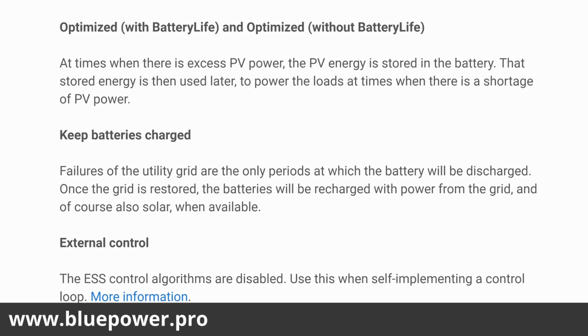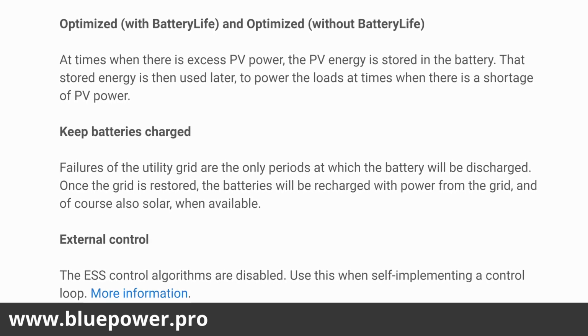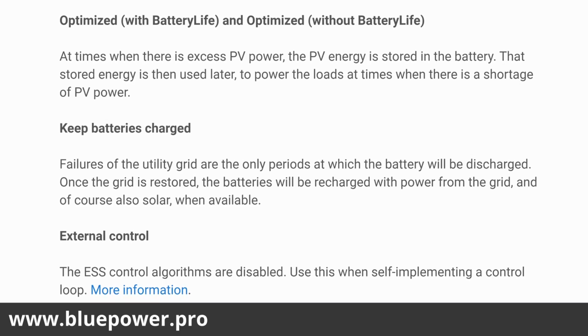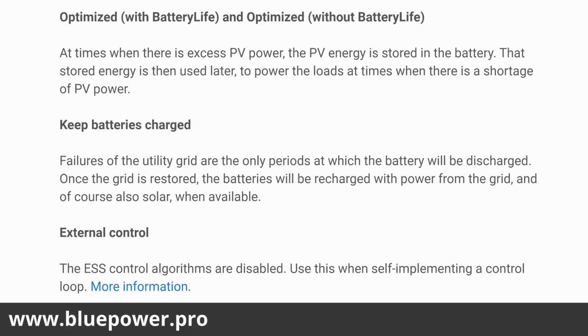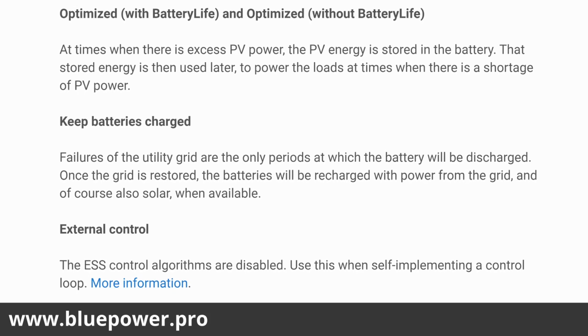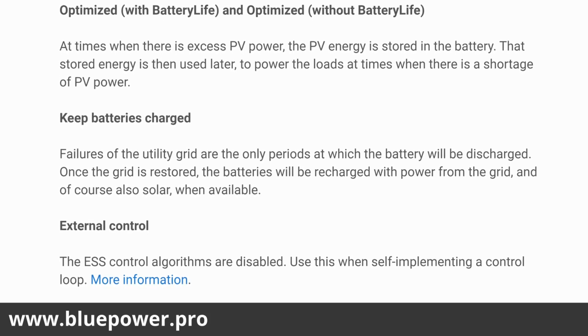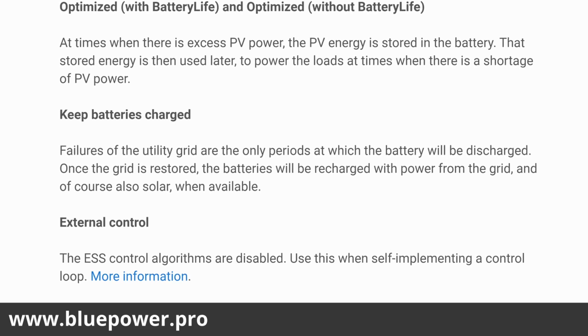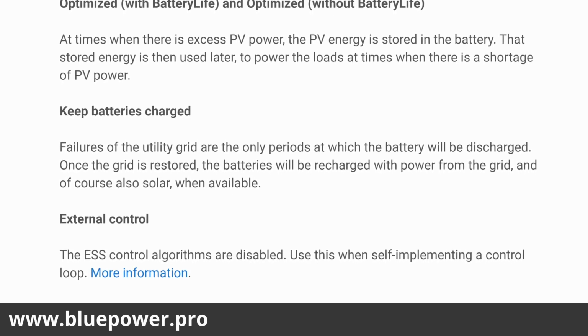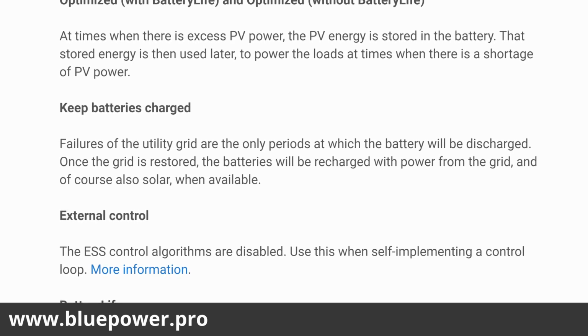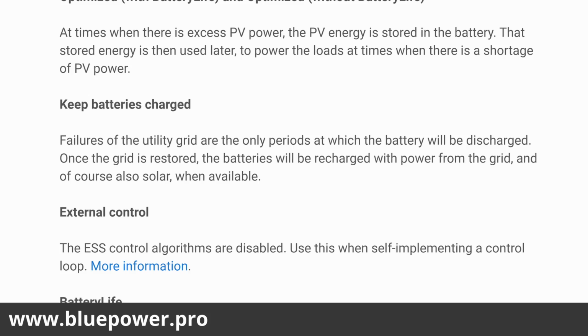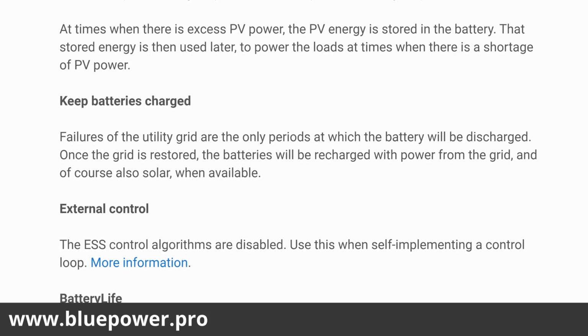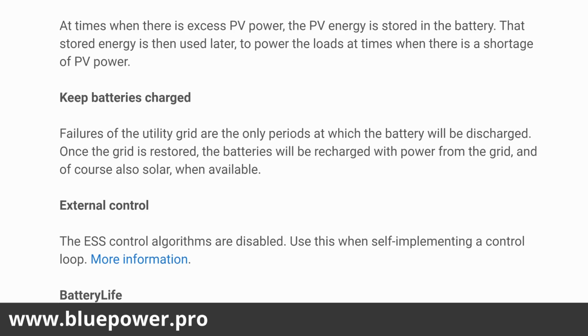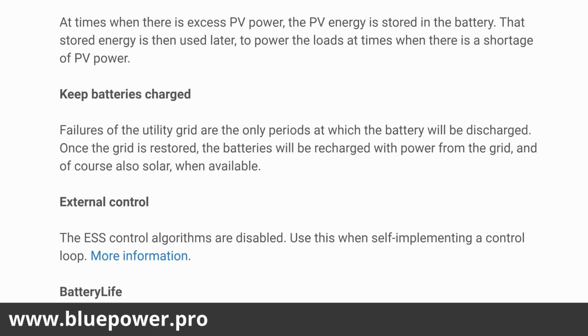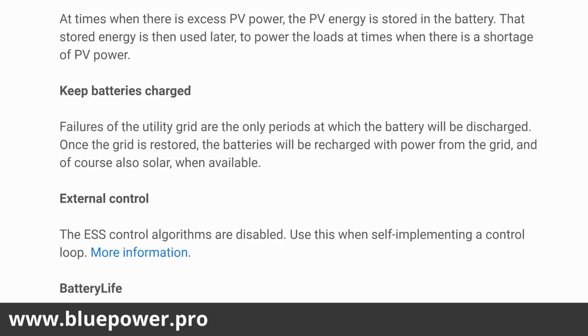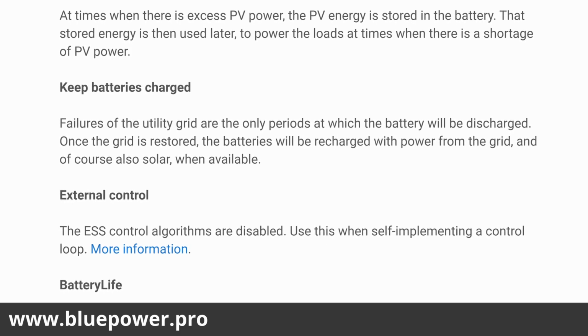So with optimized with battery life, you're going to have one option that you can set, and then the active SOC limit. You can set a minimum SOC unless the grid fails. That's the capacity of the battery bank that the algorithm is going to use to calculate how much excess PV you've used. So if you have a 10 kilowatt hour battery bank and you set a minimum SOC of 25%, you're going to have 7.5 kilowatt hours available to use maximum.